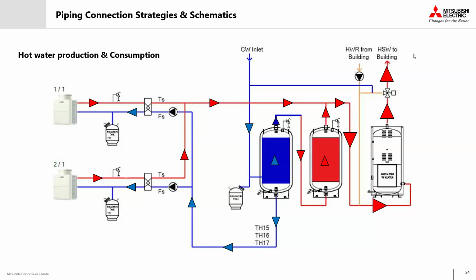Next, we'll consider this scenario where there's simultaneous hot water production as well as usage. The heat pumps are actively running and water is being consumed out in the building. Our hot water is immediately directed from the system to meet that building demand. This real-time supply draws down our stored hot water while the heat pumps work continuously to contribute to the instantaneous demand as needed, which results in effective supply temperatures during peak periods.